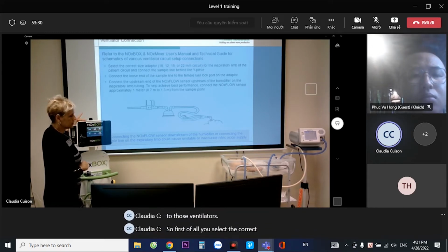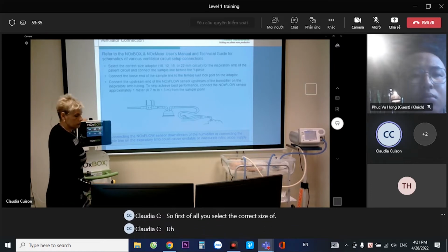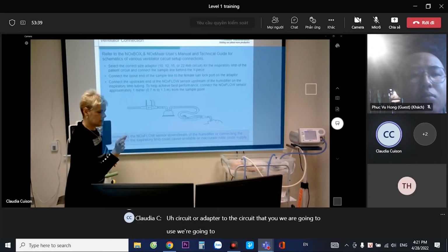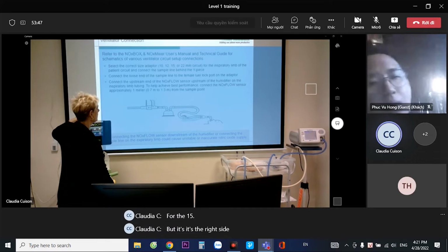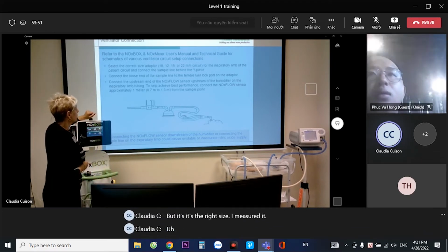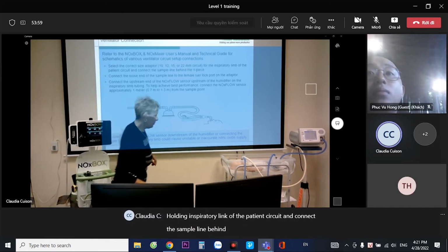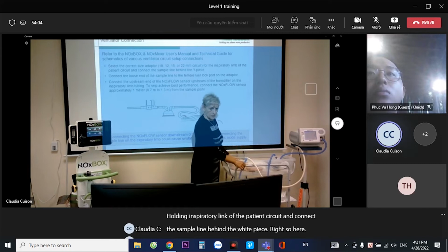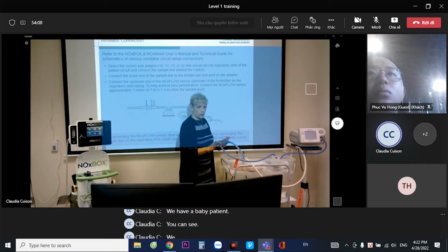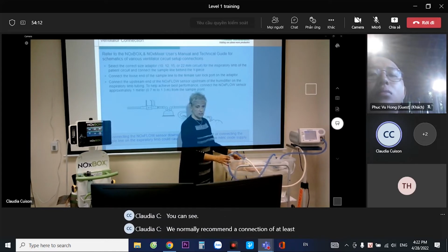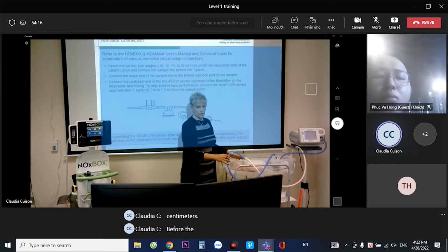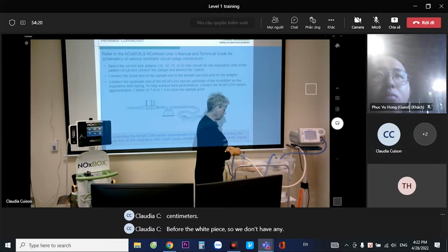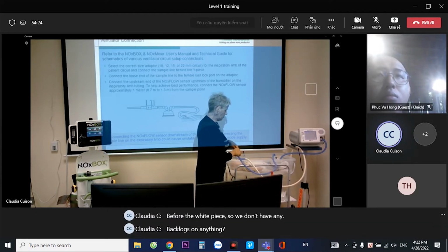So first of all, you select the correct size of circuit or adapter for the circuit that we are going to use. We're going to use this, which I think I took from the 10 millimeter or the 15, I don't remember. But it's the right size. I measured it. Select the correct size adapter for the inspiratory limb of the patient circuit and connect the sample line behind the Y piece. Right, so here we have a baby patient, you can see. We normally recommend a connection of at least 30 centimeters before the Y piece, so we don't have any backlogs or any issues with the mixing of the gases.